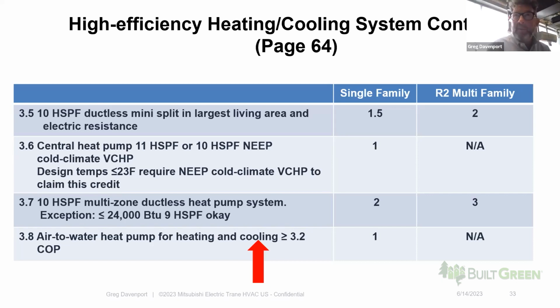I took a look at that when we were going through the code making process and suggested that if you're building a small sustainable townhome with a low heating and cooling load, be flexible with people so they can use those energy efficient multi-zone systems. So if you're building a small townhome or any small home where the heating and cooling load is under 24,000 BTU, you can go a little lower on the HSPF.